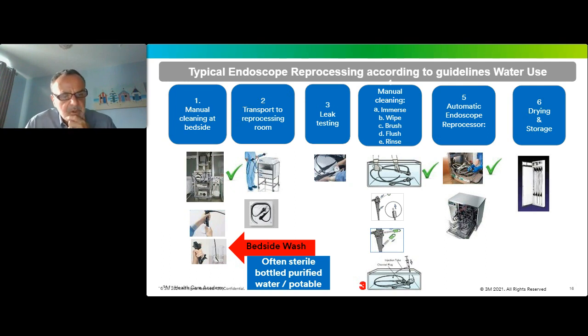Now, generally speaking, they would use bottled purified water for this, sterile bottled purified water, and ideally that's what they should use, because of course then there's no possibility of recontaminating the scope with anything other than water. If you are using potable water, then just be very aware that potable water may contain microorganisms, which could then be deposited in the channels of the endoscope, and also the chemical contamination in potable water has to be considered to make sure you don't build up films inside the channels, which could degrade the effectiveness of the scope, or indeed the effectiveness of further decontamination processes.